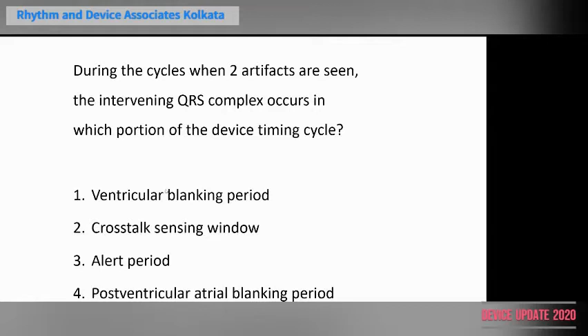So basically, after the atrial spike is given, the QRS is falling into the post atrial ventricular blanking period, and after the set atrioventricular interval. If you see from the AP to the VP spike, it is actually 220 milliseconds. So this is not being sensed, and the ventricular spike comes after the preset interval of 220. This ventricular spike actually falls in the refractory period of your intrinsic QRS and luckily does not capture the myocardium.